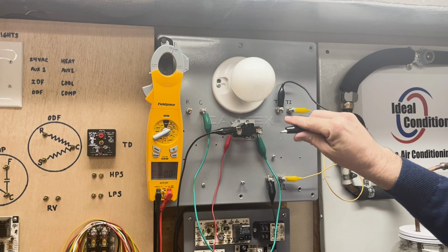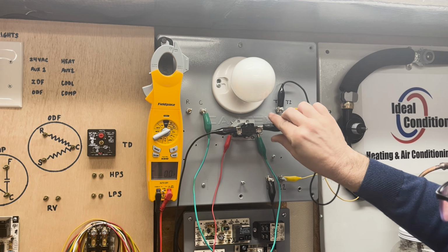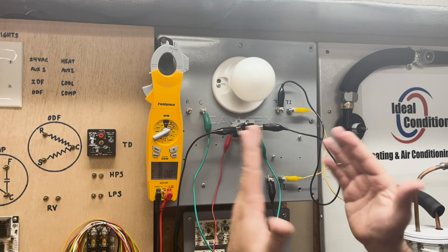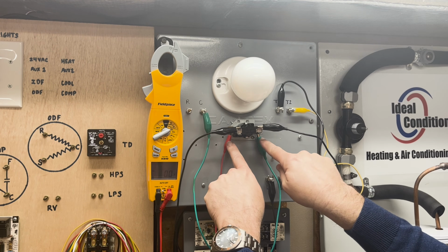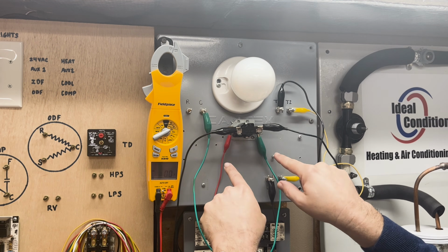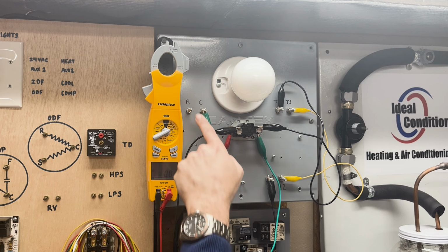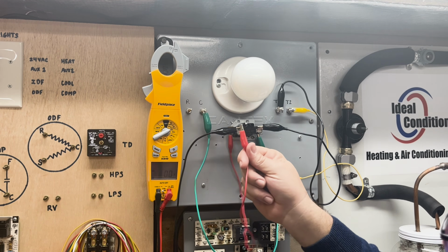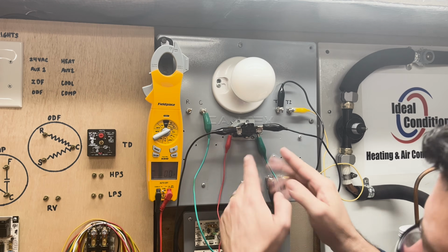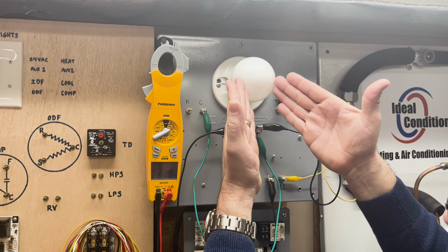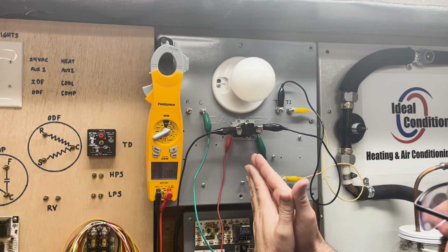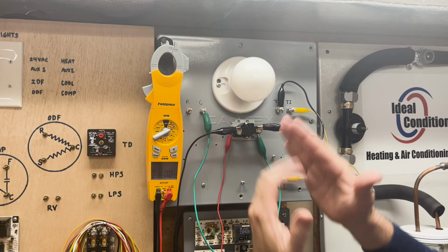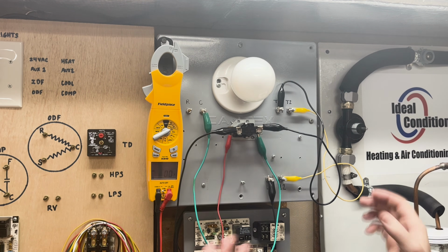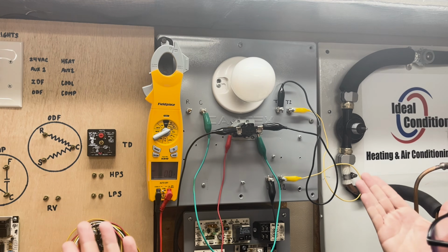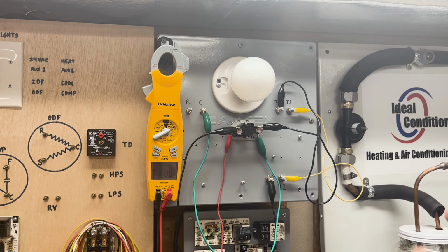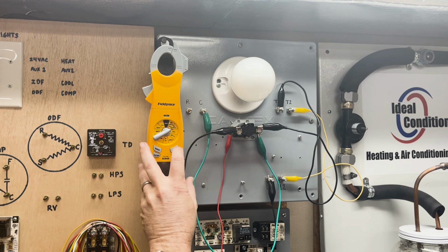Matter of fact, let's just look and look what power would be. Let's just say I had 24 volts here, even though we all know that there's not 24 volts down here because we're not hooked up, because here's the other end of it. But let's say we did have 24 volts and the load wasn't happening. Is it a bad relay? Is the relay not making? Or is it a bad load? Because there's no ampacity, so is the load getting voltage?